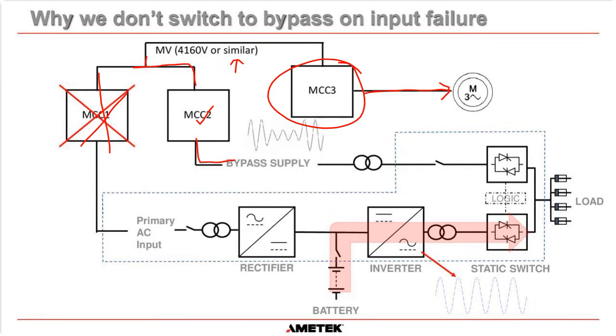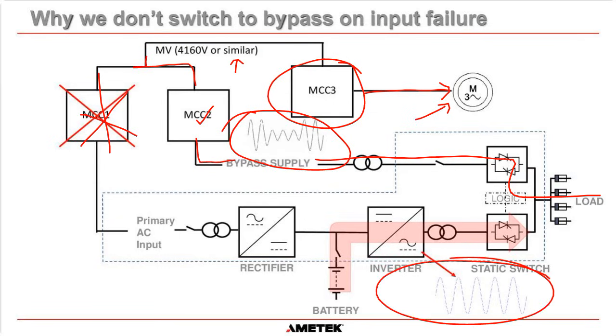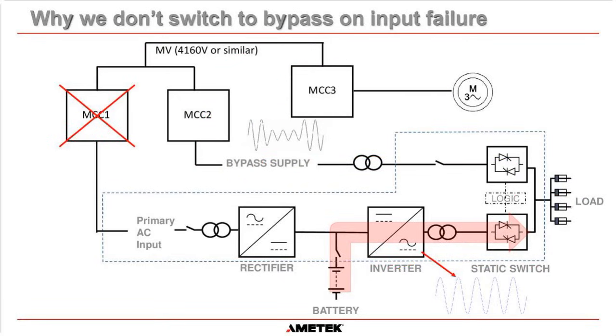So if MCC1 fails, which causes a domino effect on some of the plant, and a control signal gets sent to these motors to say, oh, there's something going on, you need to turn this pump off, then turning on pumps and turning off pumps is going to cause disruption on this bypass supply. And we don't want that to be seen by the load circuits. So the inverter is going to be perfectly nice, a beautiful sine wave, while all of this messy stuff is going on in your plant MCC.